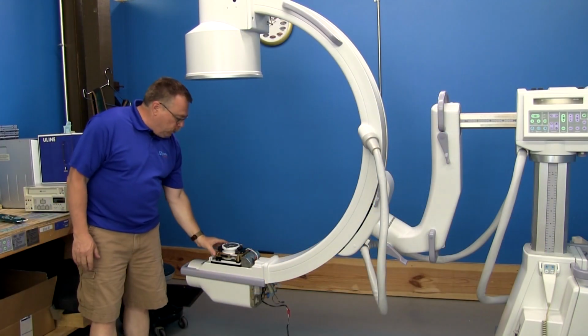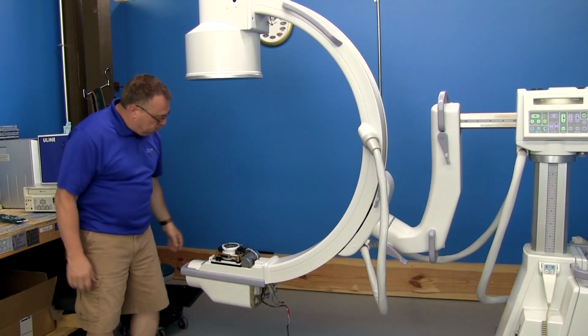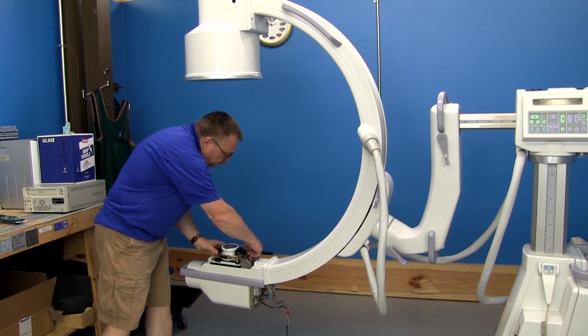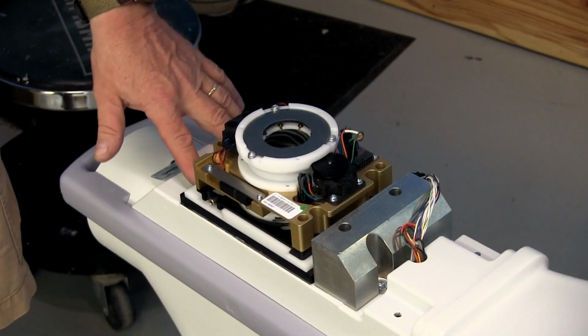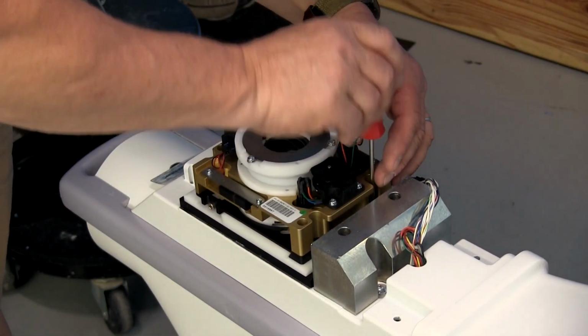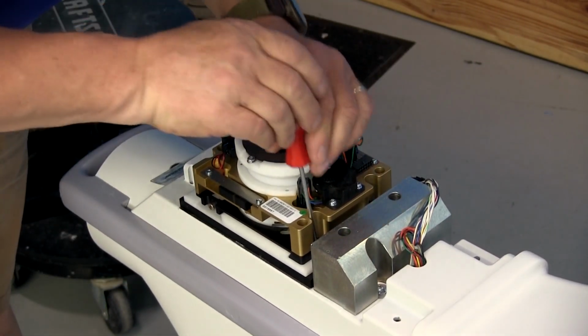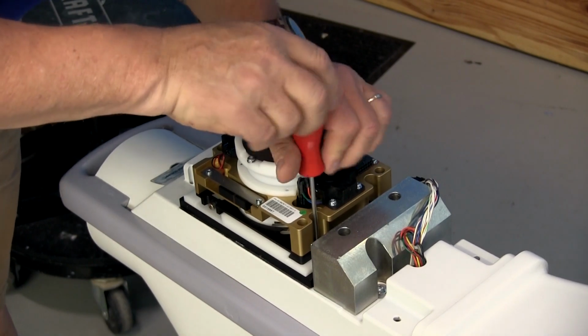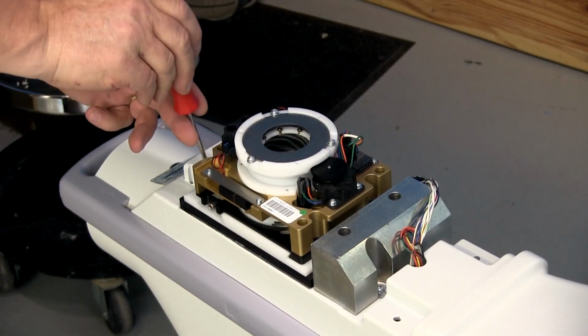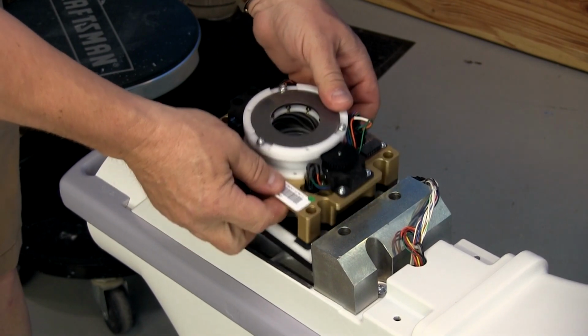The next step is to remove the collimator. It's got one connector. The collimator has four screws, two in the front and two down here below. Just loosen all four of those, and then the collimator lifts straight up.